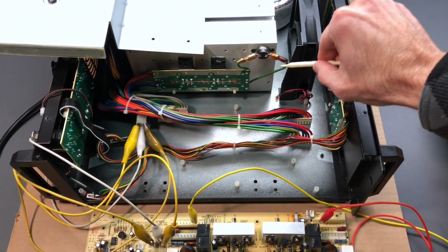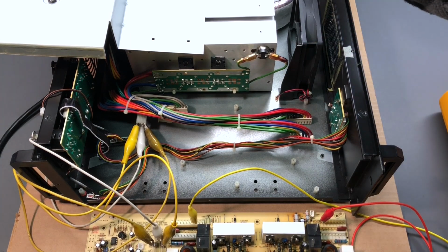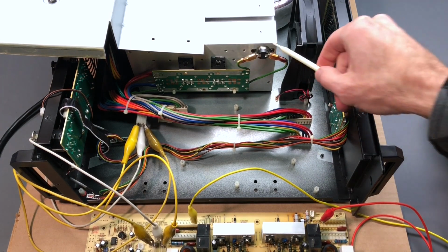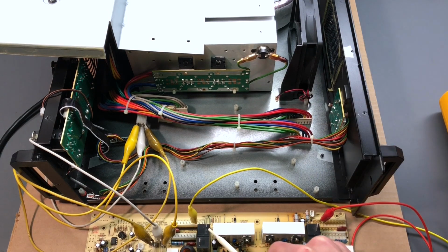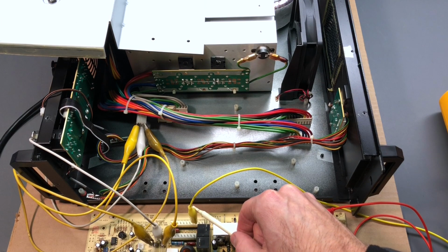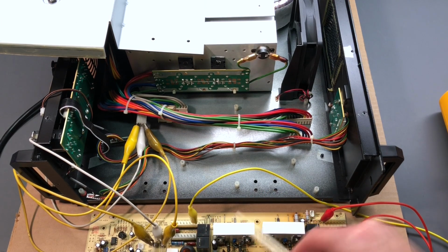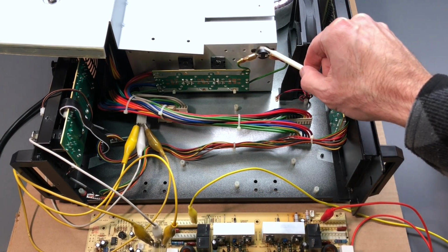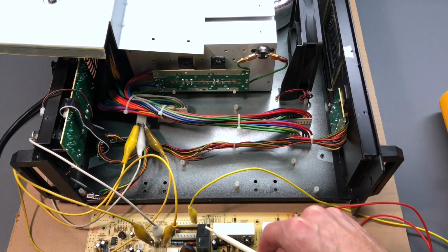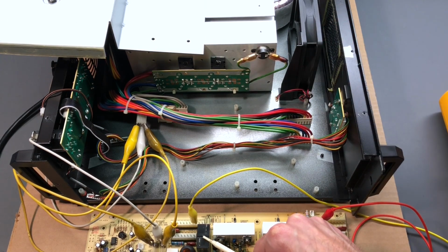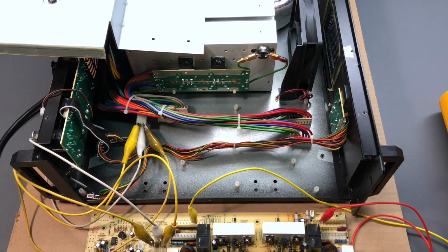This temperature sensor right here with the green wires, and then there's another one over here with green wires, are wired in series with the coil in the relay. If you break this connection and don't have it closed, the relay will not energize, so these are normally closed. If there's an overtemp condition, they would open, causing the relay to shut off, and its contacts would then open.